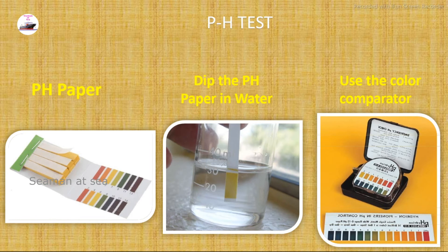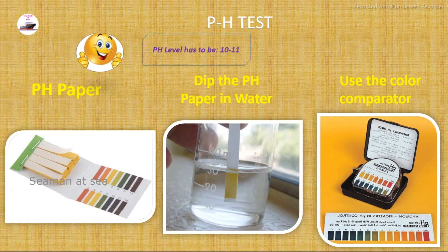For the pH test, we take a pH paper and dip it into the boiler water. The color will start to change. We then check with the color comparator, which shows us the pH value present in the water. The pH level should be 10 to 11 — this is the acceptable value by every surveyor.